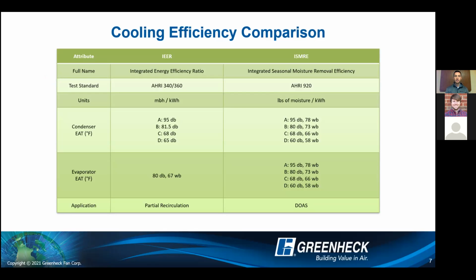So the first one is that IEER value, or that integrated energy efficiency ratio. So that is the part load condition that is tested to standard AHRI 340/360. And it's really looking at the MBH per kilowatt hour to determine the efficiency. So if you compare that to the ISMRE, if you've ever seen that, it is standard AHRI 920. It stands for Integrated Seasonal Moisture Removal Efficiency.